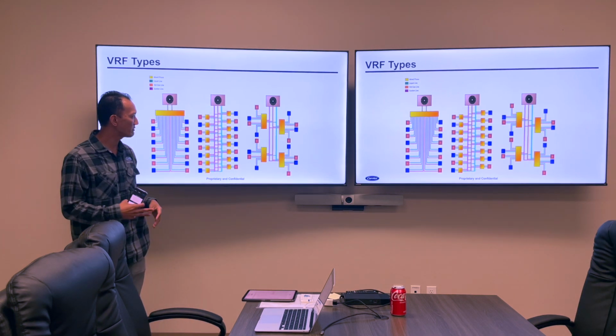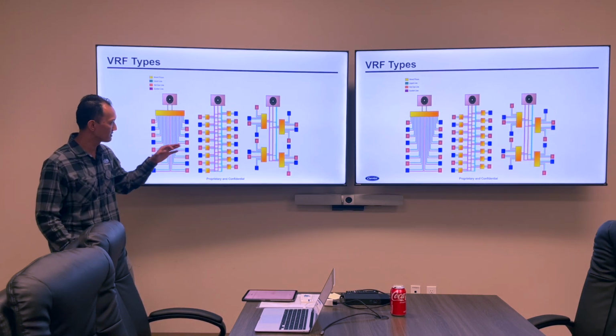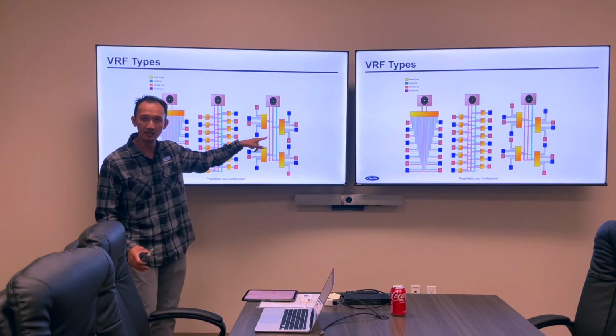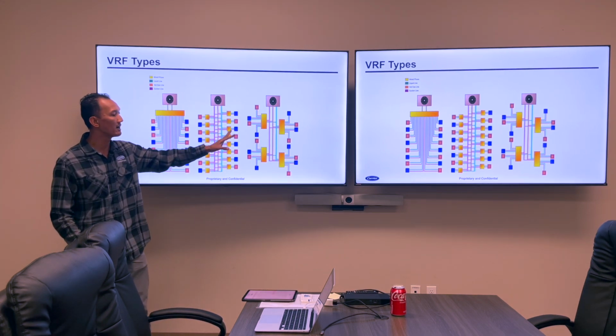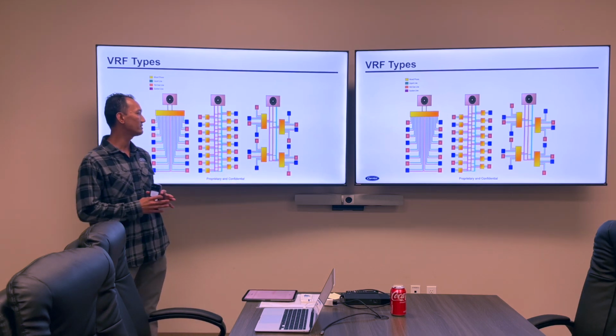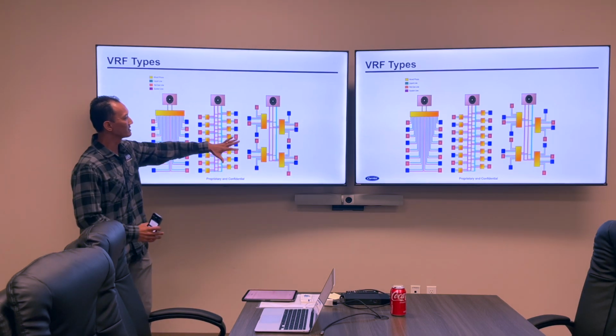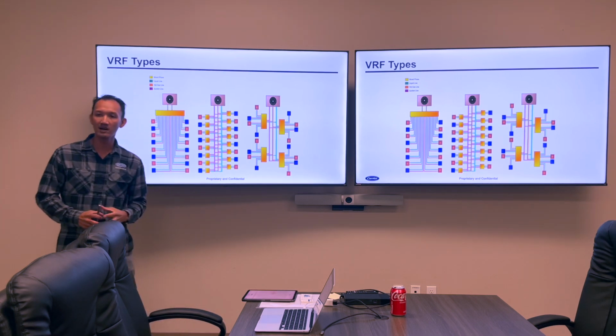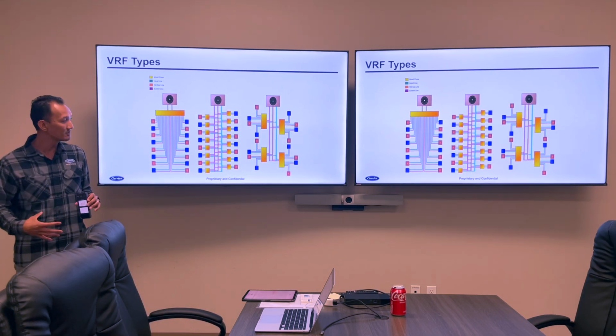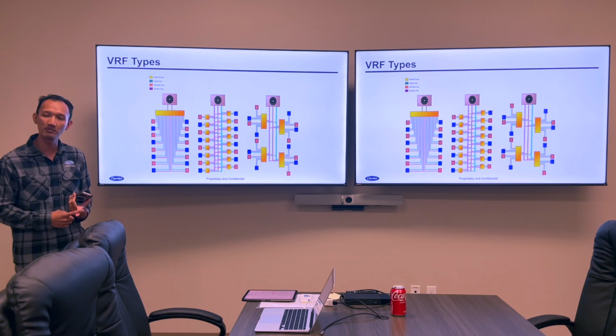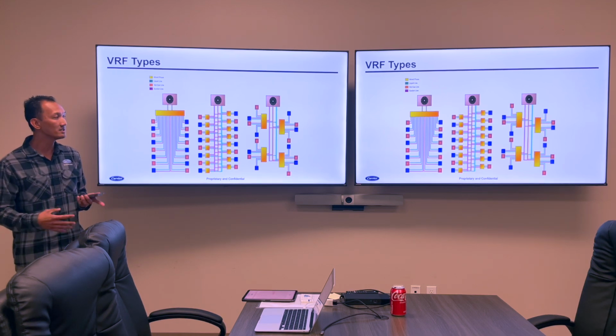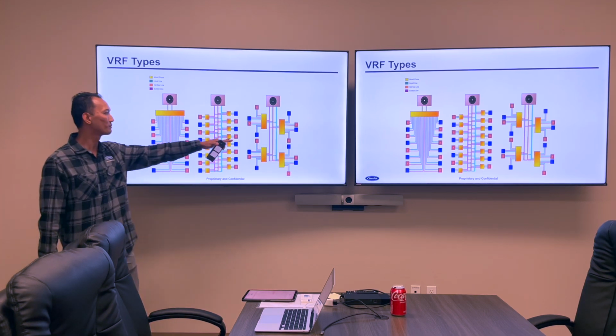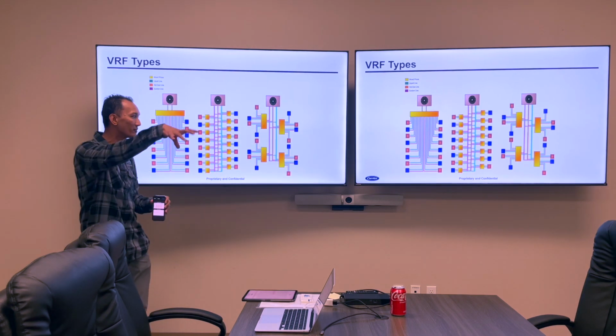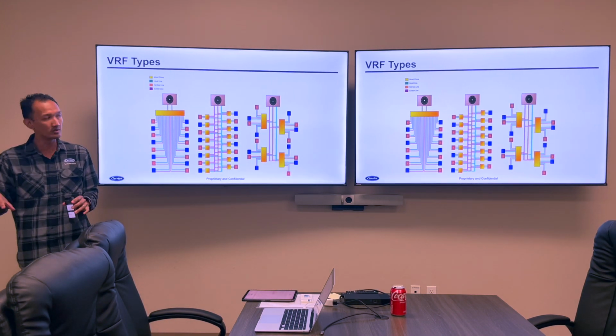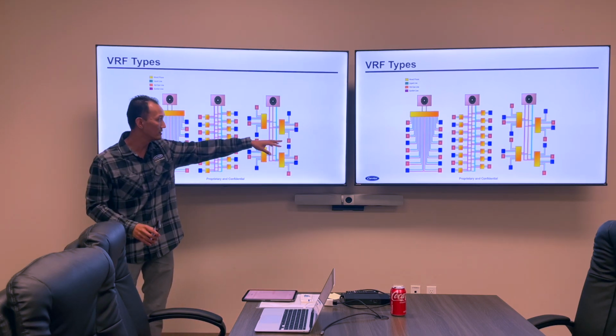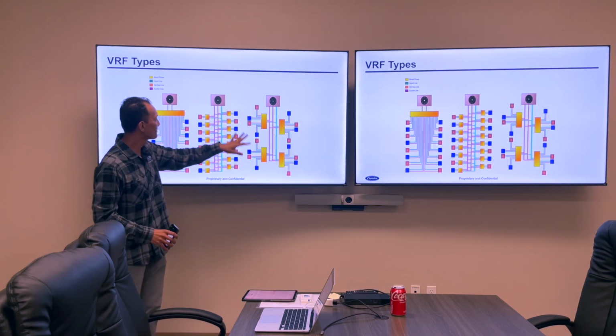Three-pipe heat recovery, we have a little bit more flexibility as far as the flow selector boxes. They come in single port boxes, and we also have 4, 8, and 12 port varieties. This allows us to kind of strategically place these flow selector boxes wherever we need to in the space. So like in a hotel application or like a mid to high rise office building, you can strategically place these on different sides of the building or different corners of the building, and then you can pipe out and zone to the different fan coils.